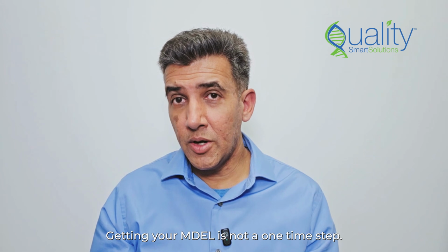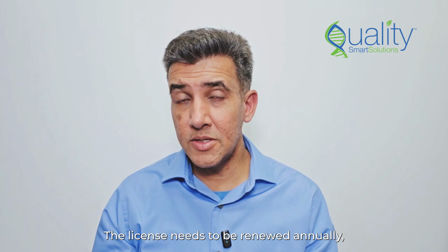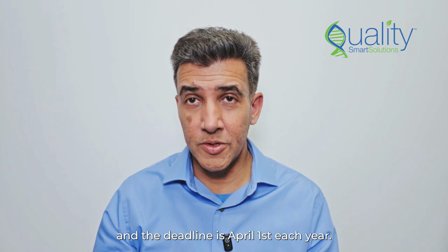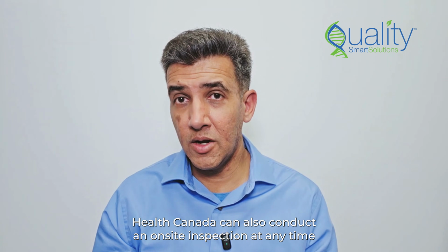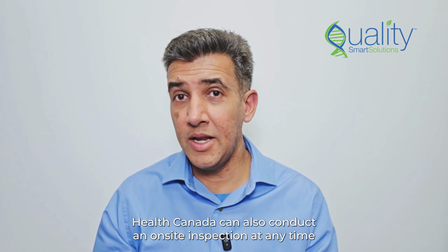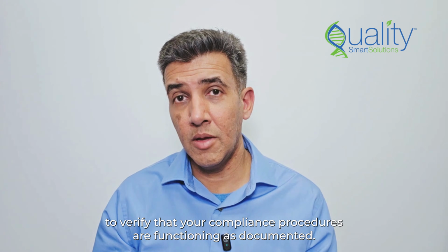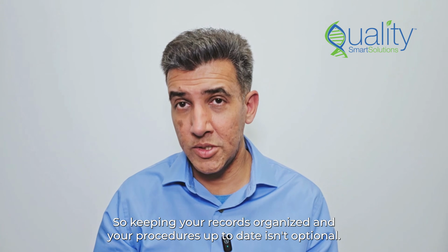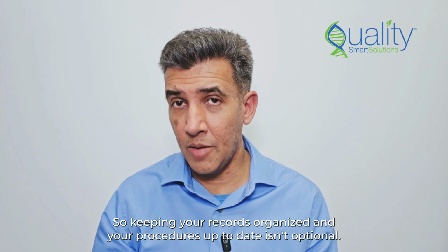Getting your MDEL is not a one-time step. The license needs to be renewed annually, and the deadline is April 1st each year. Health Canada can also conduct an on-site inspection at any time to verify that your compliance procedures are functioning as documented. So keeping your records organized and your procedures up to date isn't optional.